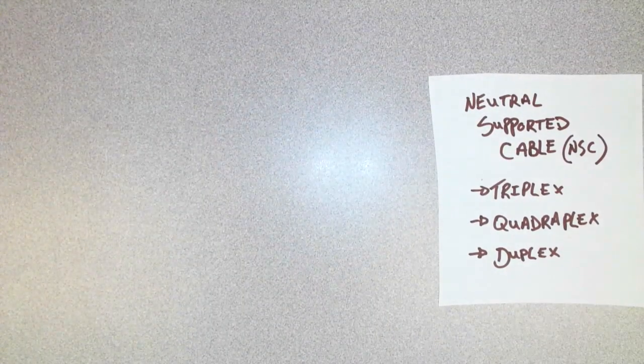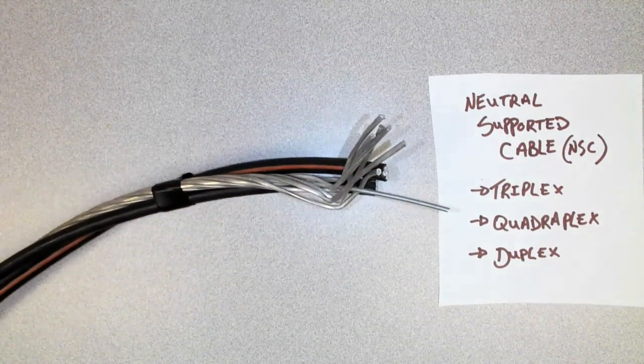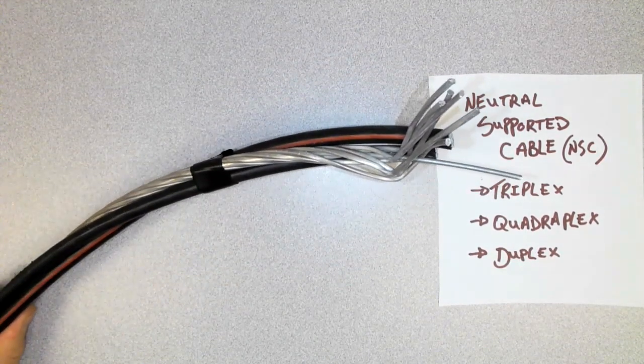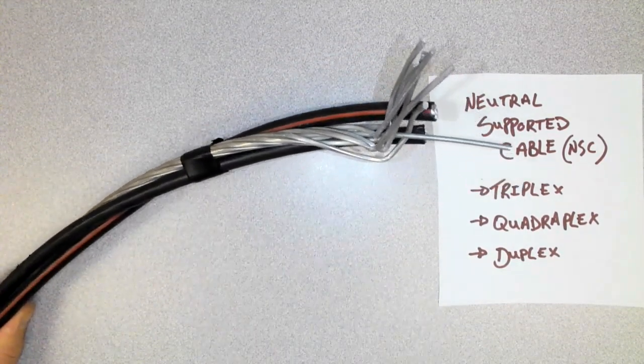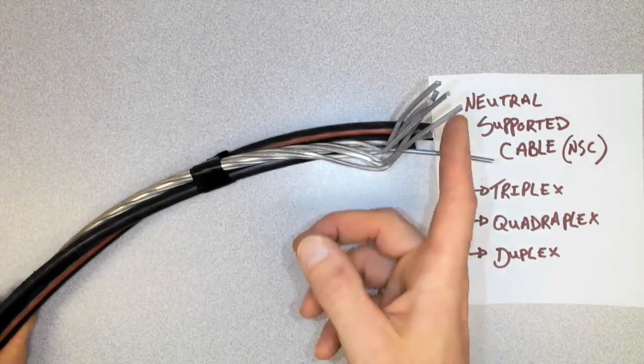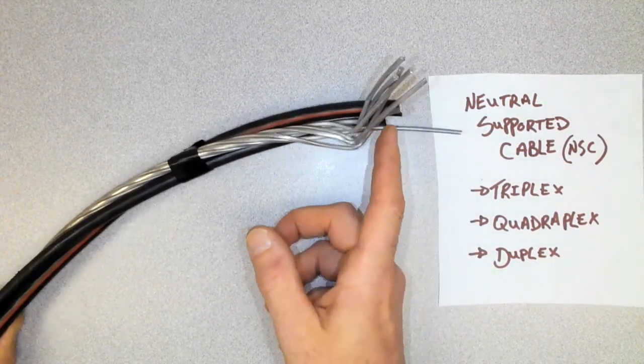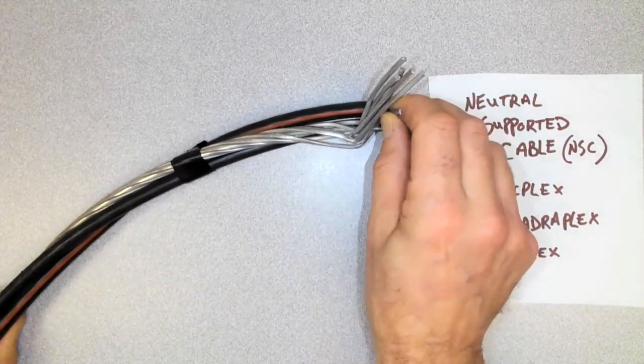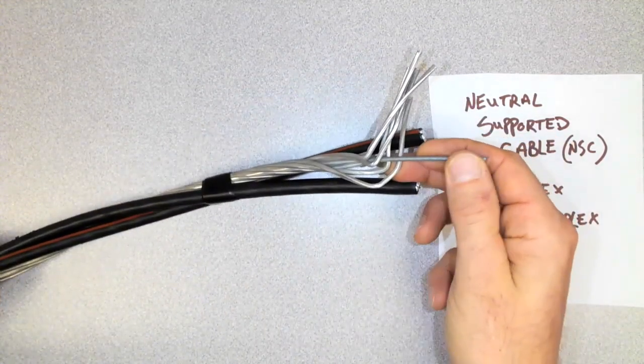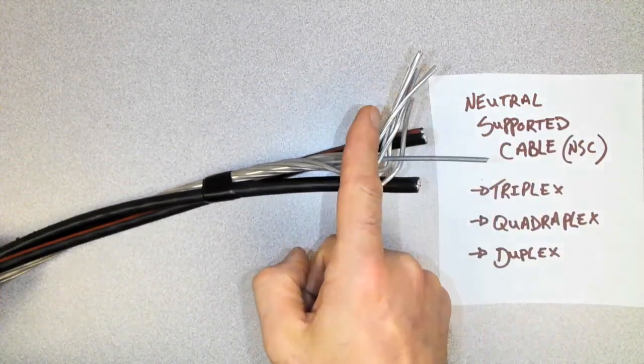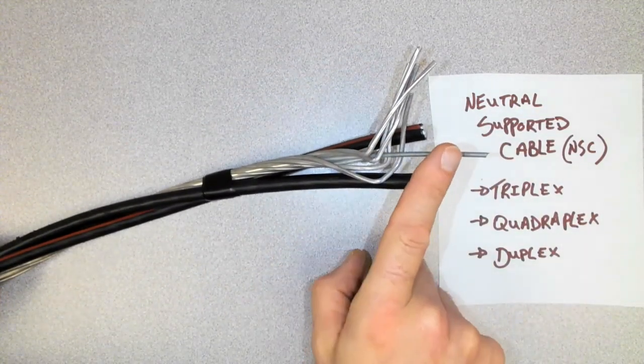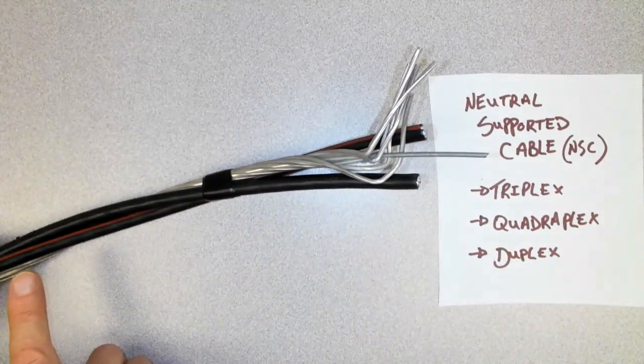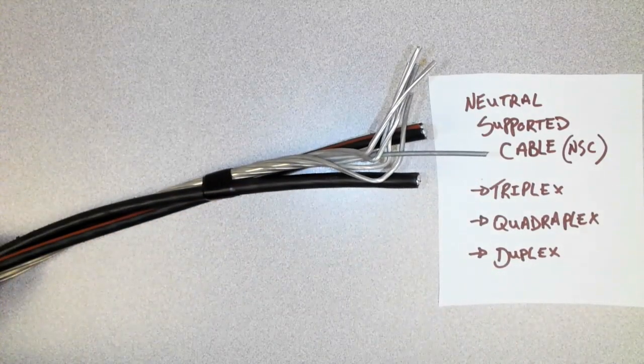All right, let's take a look at another one. We're going to look at a neutral supported cable, or NSC as it's known in the code book. Neutral supported cable is used for overhead applications, and this is a good example. We've just got tape on here to keep it together. There are two insulated conductors. There is a bare bonding conductor, and one of them is just sticking straight out, and that's because it's not made of the same material. This is steel, whereas all of these are aluminum. And this is meant to support the entire span of this suspended cable in midair.